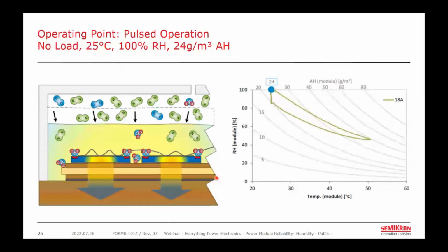Now, power modules are designed so that most of the heat generated by those chips flows down through the substrate, through the base plate, and into the heatsink. So if we're continuing to cool that heatsink, even after the chips have stopped switching, we could potentially cool the chips and substrate faster than the silicone gel can cool, and possibly faster than the time it takes for the water molecules to move out of the gel. And so if the temperature of the chip drops below the temperature of the gel, which is at 100% relative humidity, as we just described, the water molecules will condense onto the chip surface, and we have the problems we described before.